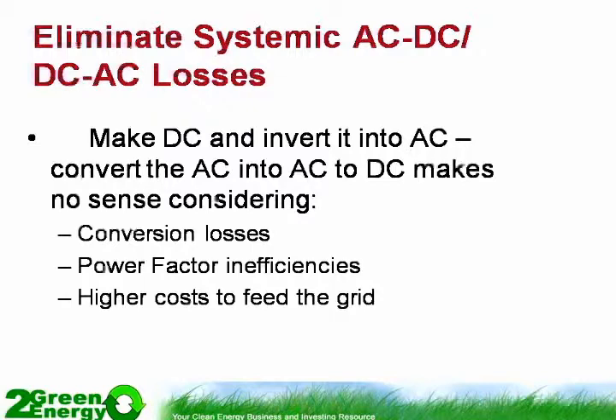When you're using DC, you don't have power factor issues. And if you're going back the other way with photovoltaic and selling back to the grid, you have the cost of the inverter, the cost to intertie with the grid, and also anti-islanding issues, where if the AC grid power goes down, your solar panel array gets turned off so that linemen fixing the lines don't get shocked by solar being injected back into the grid.